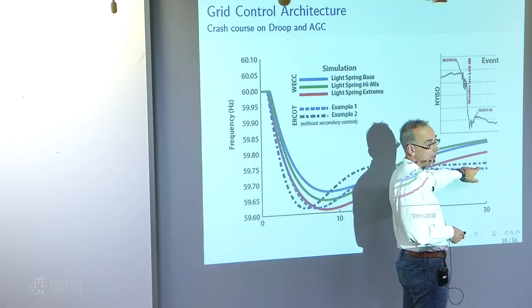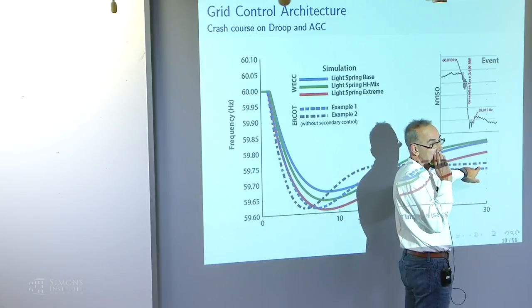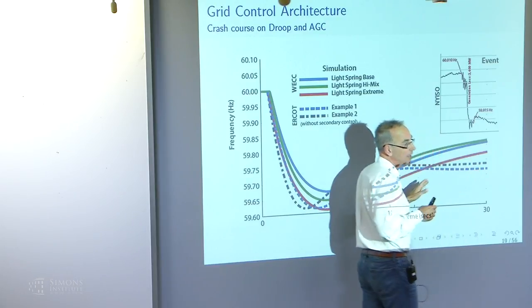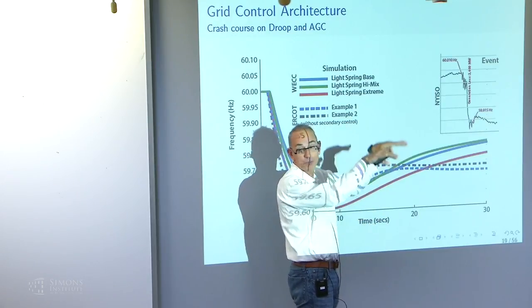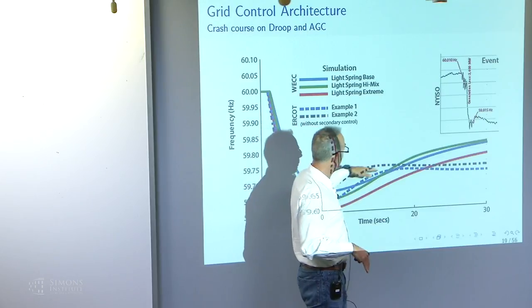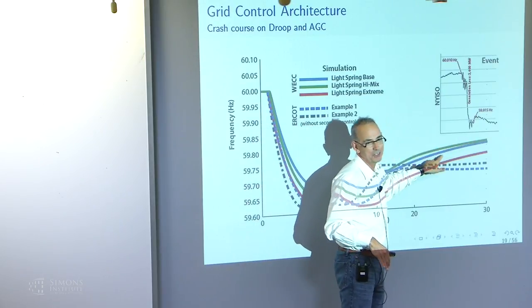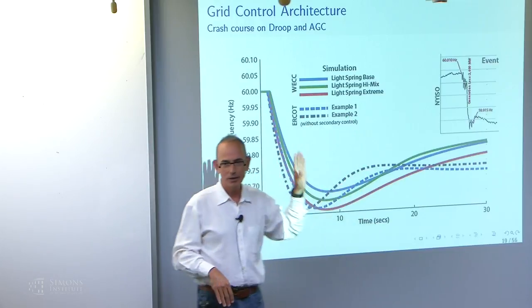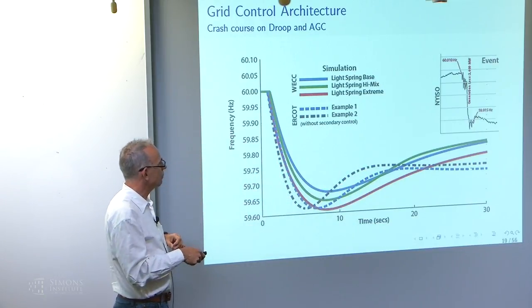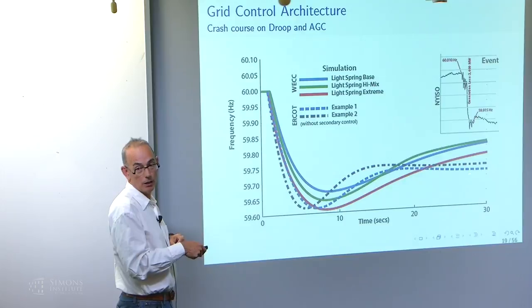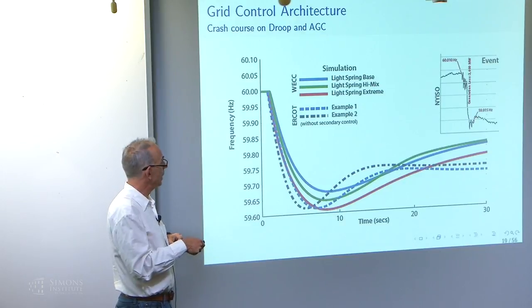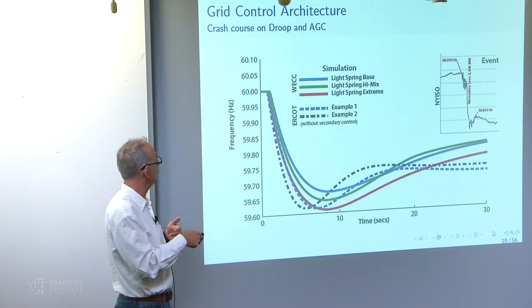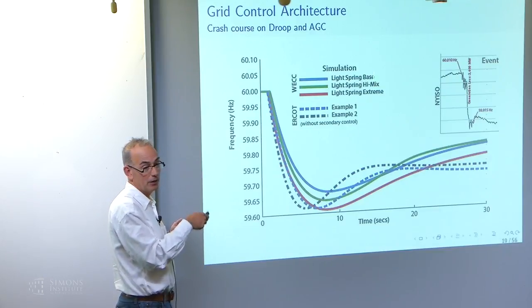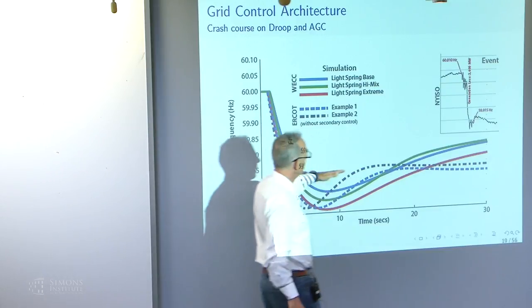That's if the balancing authority isn't saying, hey, step on the gas. In reality, the balancing authority uses PI control, trying to bring the frequency back up—so it goes back up like this. These are simulations from WECC, the Western Interconnection, showing what happens if the balancing authority didn't do anything after a loss of load or generation. But in fact they have PI control, so they measure the frequency error, integrate it, and send a signal.